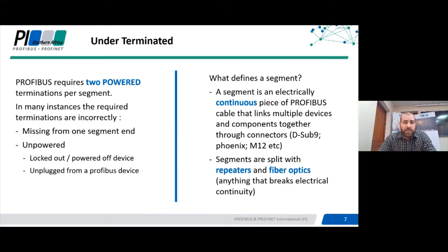This results in reflections, or alternatively the terminations are unpowered. A terminating resistive circuit requires power to create an idle voltage on the bus and protect it from interference and impedance related faults. The power for this termination circuit often comes from the device the Profibus connector is connected to. If this device is locked out, powered off, or the terminating plug is disconnected and just left in the panel, then the idle voltage — which requires at least one volt — will not be maintained, and you will suffer from interference related issues.